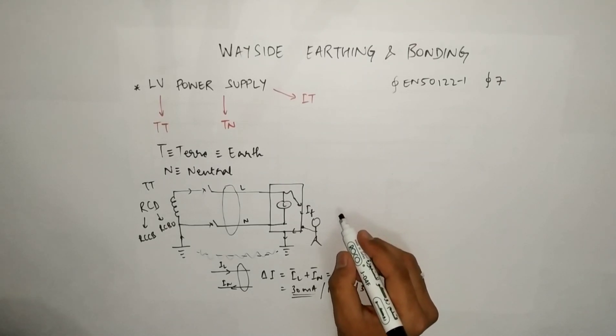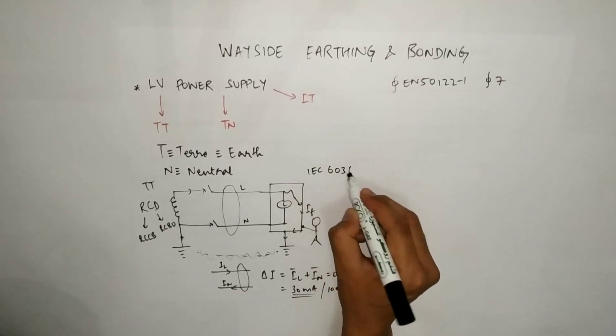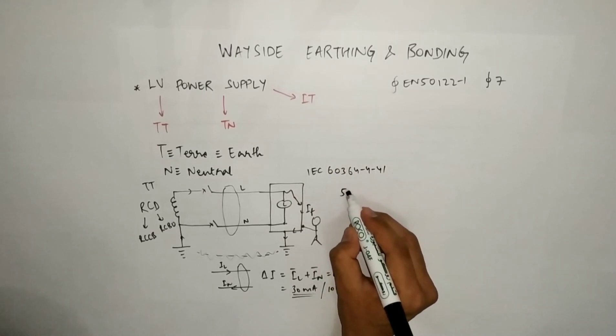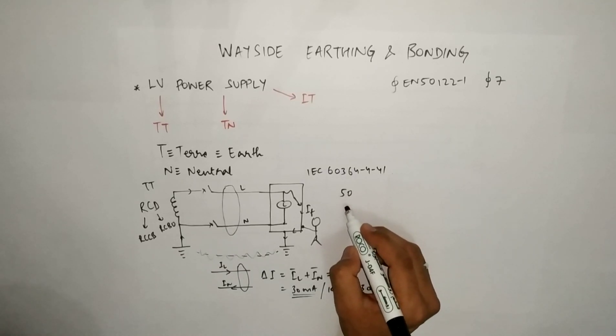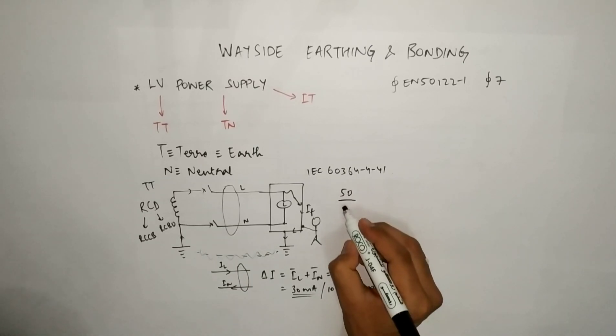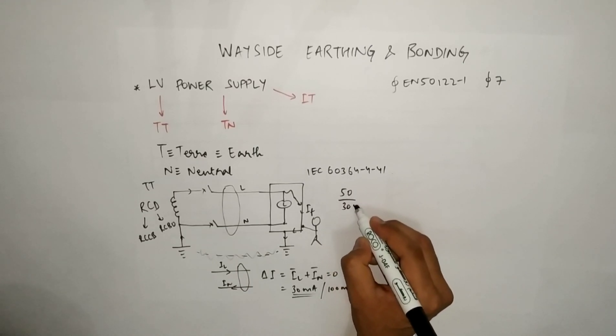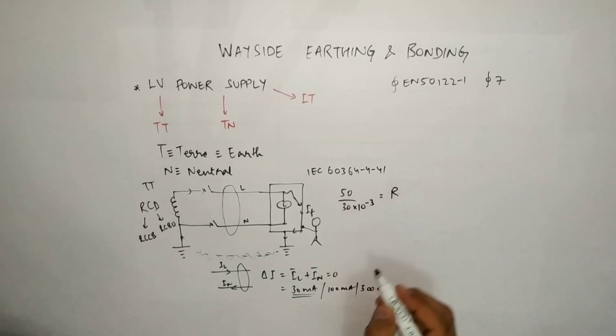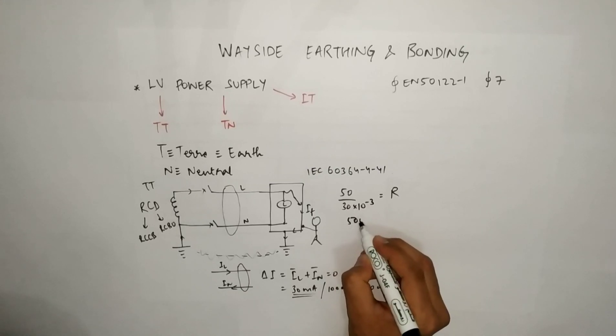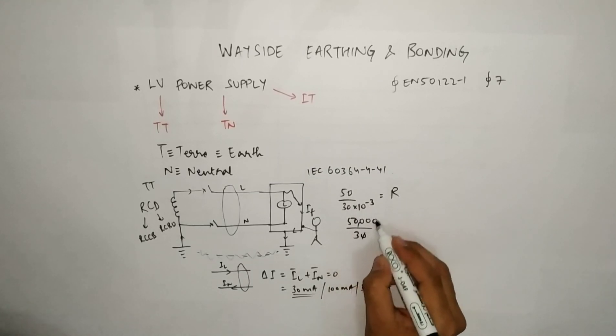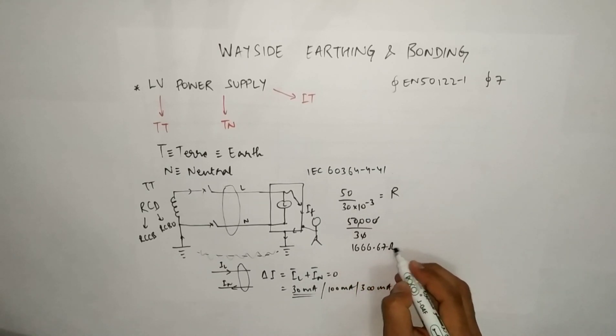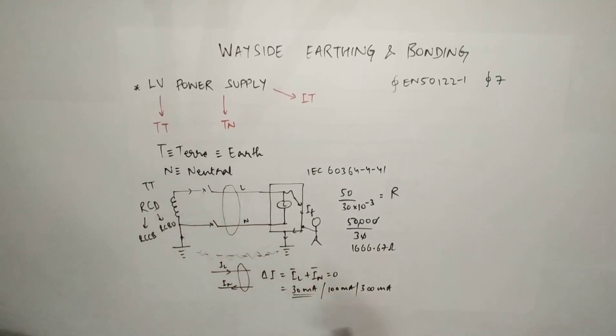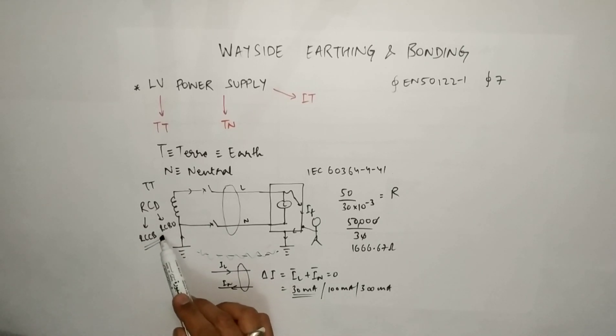As per IEC 60364-4-41, the safe voltage for an AC system for a person is around 50 volts. If the voltage is 50 V and the current flowing is 30 mA, you can calculate the resistance: 50 divided by 30×10⁻³ gives a value of 1,666.67 ohms, which is very high. So even if the resistance of this path is very high, the RCCB will still trip. That is why we always recommend going for an RCCB.